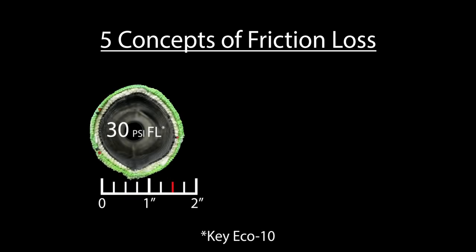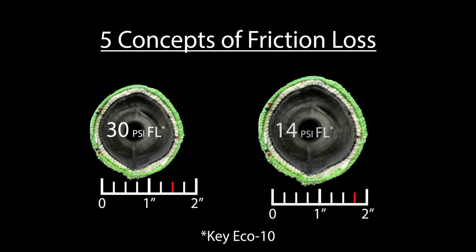For example, increasing the hose size by only a quarter of an inch, from one and a half inch to one and three quarter, will cut the friction loss in half.